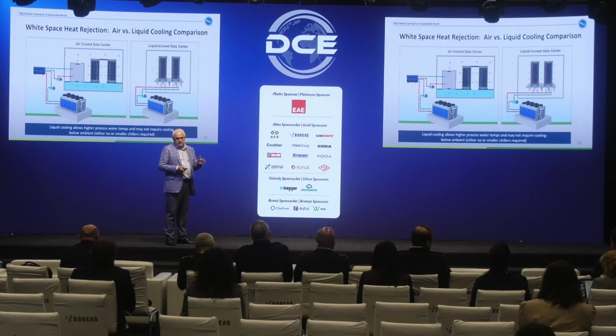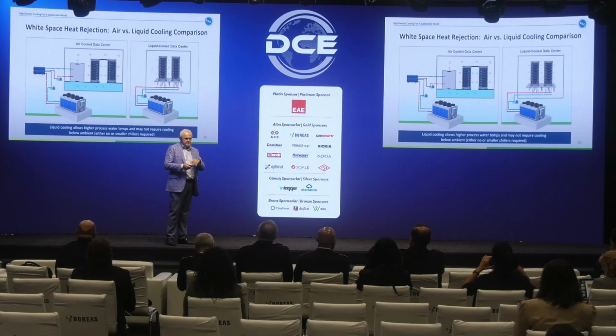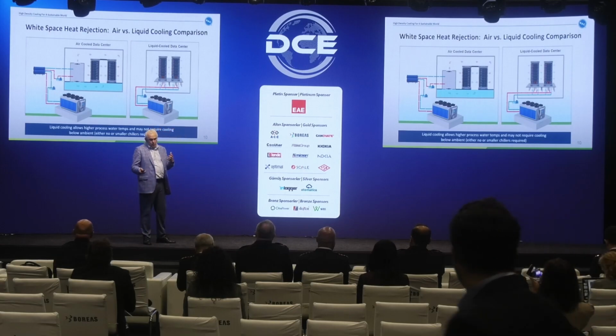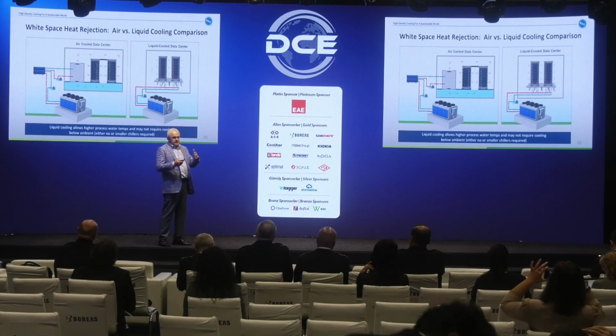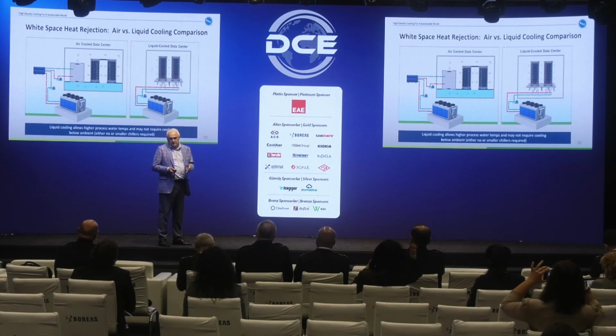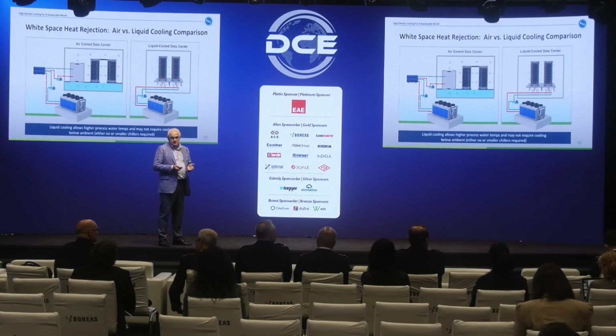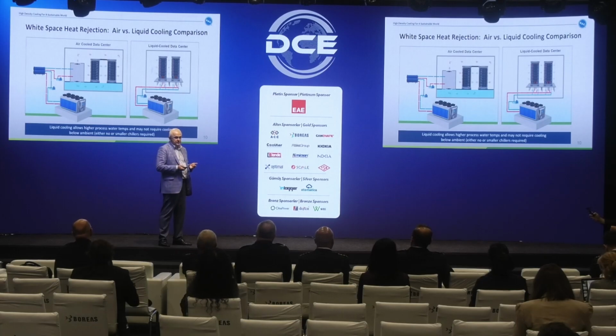So now, the great benefit of eliminating the chiller is getting free cooling, which is the terminology of the industry. Of course, it's not really free since you are still using some fans and pumps, but when you get rid of the compressor, which represents 90% of the electricity, it is almost free. So now you see that the chiller, as I said, became the bad guy in the room. With liquid cooling with cold plates, this is an example of the temperature range: when you operate in the range of 28 Celsius, you don't need a chiller. You can use a fluid cooler to cool the water, let's say from 38 down to 28, or 35 down to 28. You don't need a chiller.